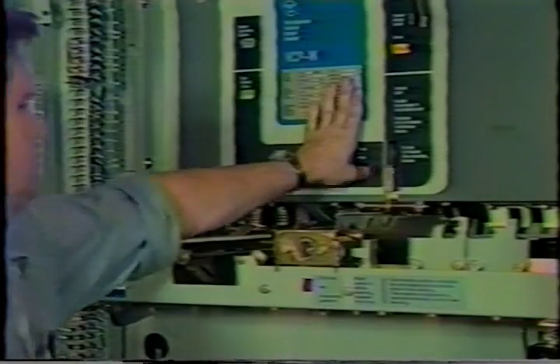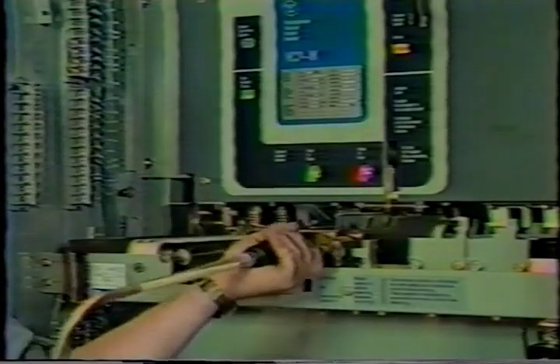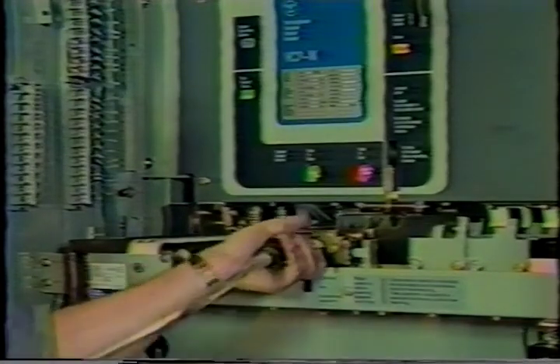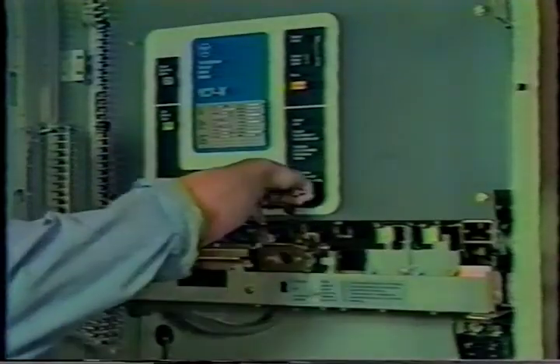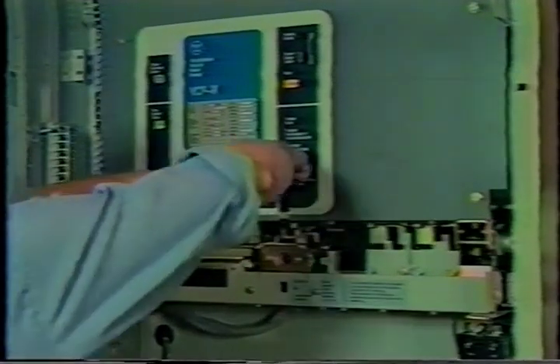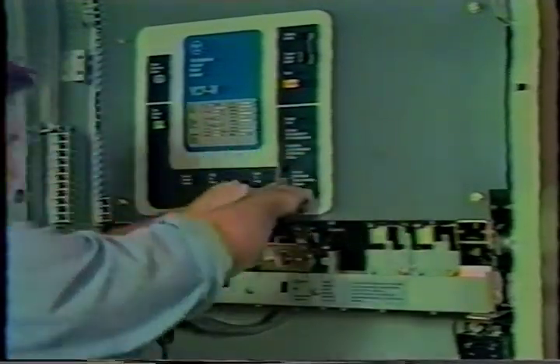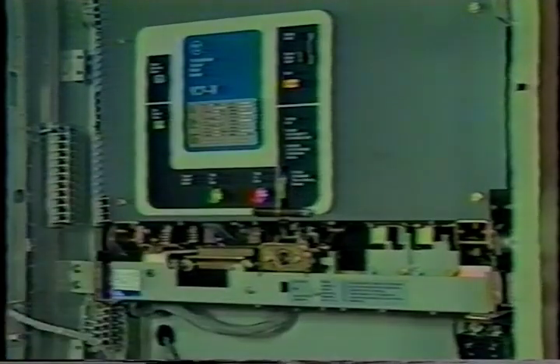Now, trip the breaker and move it to the test position. The extension rail interlock prevents the breaker from being withdrawn out of the enclosure unless the extension rails are engaged to the fixed rails. If the breaker functions correctly, it is ready to be put into service.